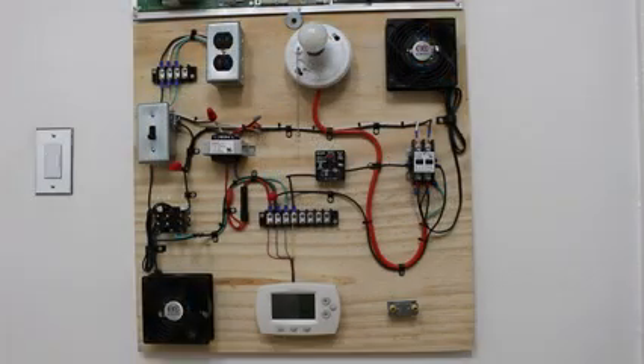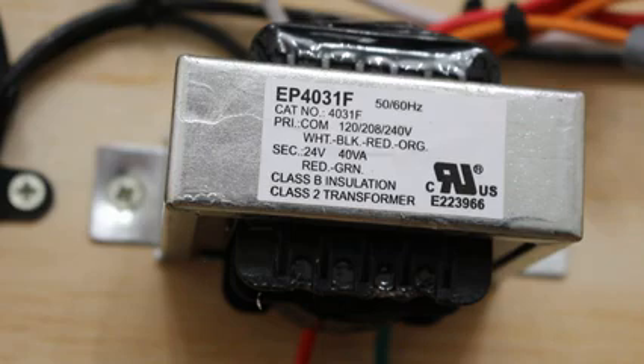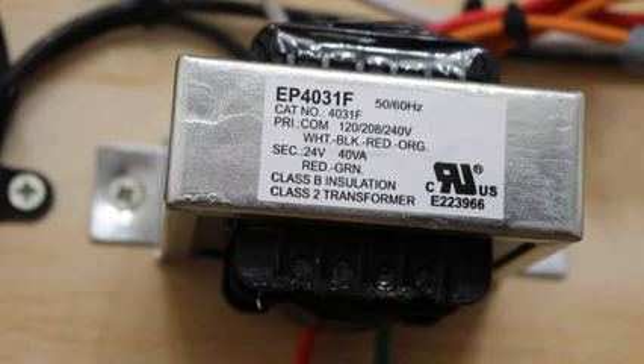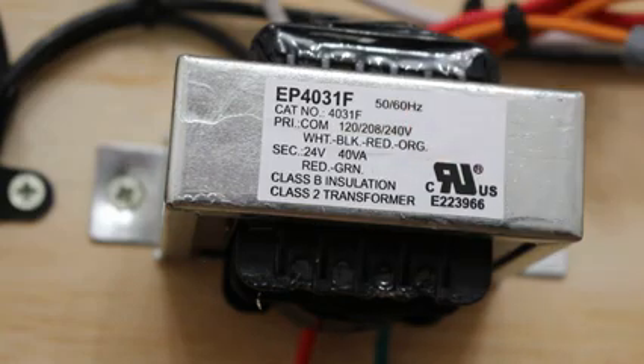This is an electrical training board that I designed and created, and what we're actually looking at is an air conditioner. The way we're going to troubleshoot this transformer is by first identifying what we're working with. If there's a label, definitely pay attention. Read what you can. A lot of times you're not going to be able to read it. So a good way to find out your primary voltage is to look at the voltage of the system you're working on. If this happens to be a 208 volt system, chances are 208 volts is going to be your primary voltage. If you have a 120 volt system, 120 volts is going to be the voltage you're looking for at your primary.